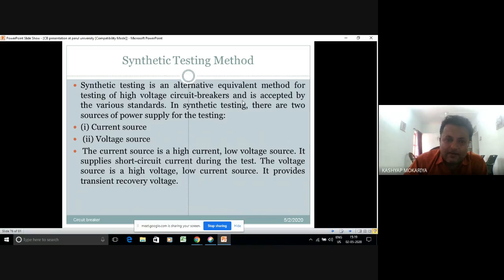Synthetic testing is an alternate, equivalent method of testing high voltage breakers and is accepted by the various standards. In synthetic testing, there are two sources of power supply, a current source and a voltage source. The current source is a high current, low voltage source. It supplies short circuit current during the test. The voltage source is a high voltage, low current source. It provides a transient recovery voltage.